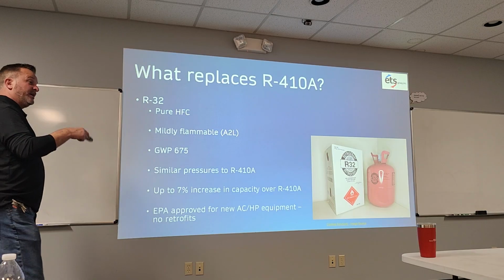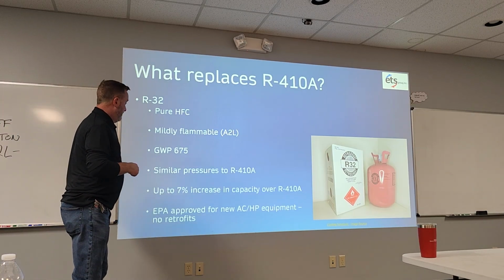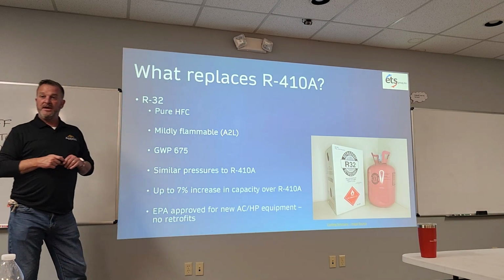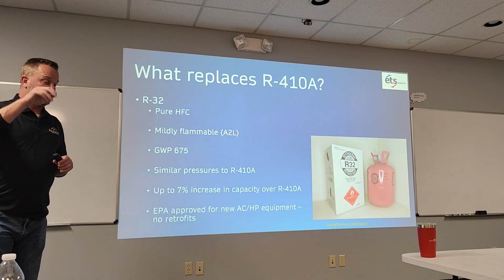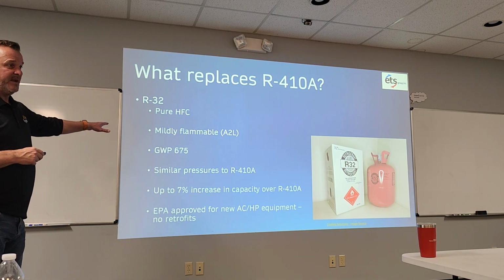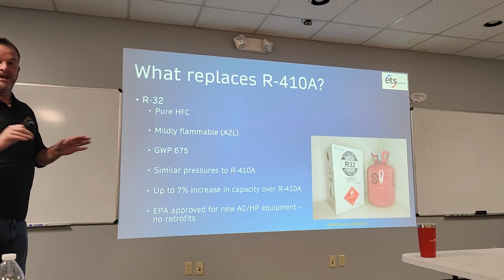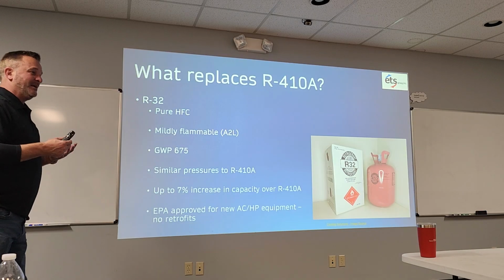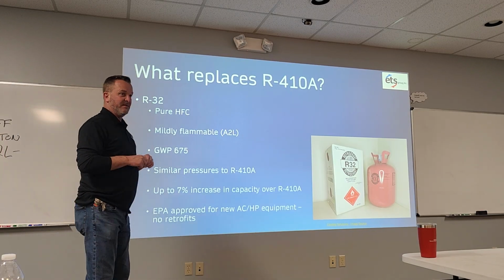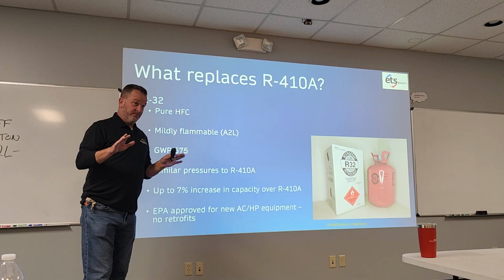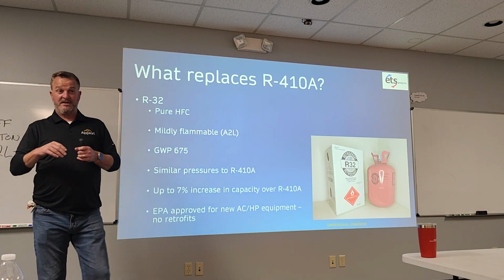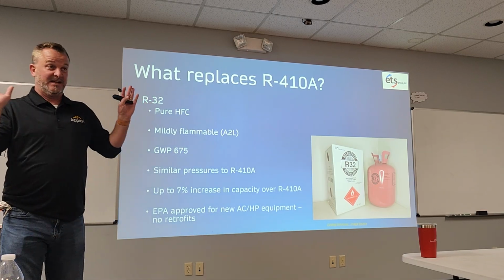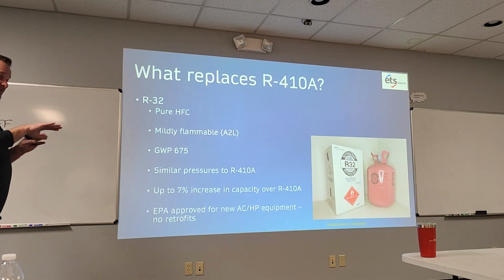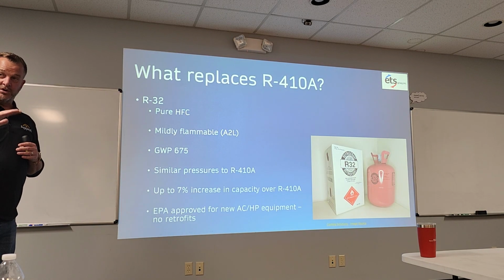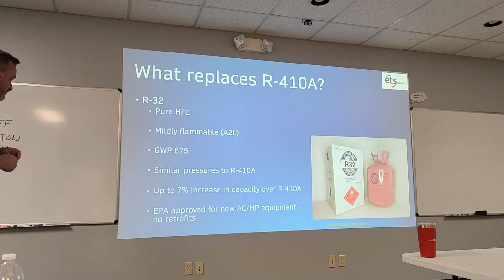At the very beginning in 2020, when they were talking about a lot of this, that was bantered around - that they wanted everything under 600 past 2030. There is no such regulation. There's no EPA papers, no EPA documentation. So if somebody tells you, oh I'm not going to use 32 because it's not going to be around in 5 years, not true at all. As of right now, unless they come out with some new regulation - which I never say they won't - but as of right now there's no such thing as that. A lot of people out there are peddling that it has to be 600 and below in order to be used past 2030, okay?